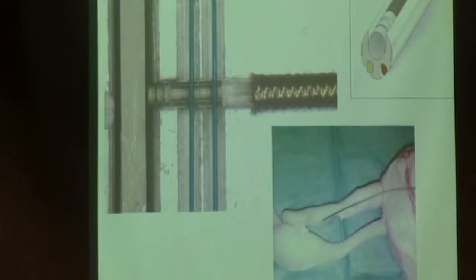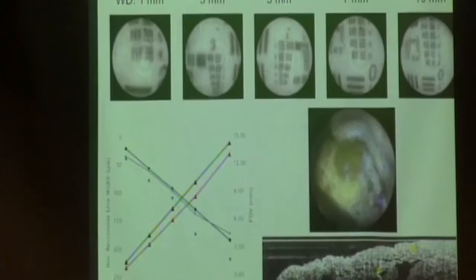It looks like, from an endoscopic view, it looks like human tissue. It kind of feels like human tissue. It's about as slippery as human tissue, and so that was really helpful for our testing. We went through and we did some performance measures of it, and it is beautiful. It really is. I'm super proud. Considering this thing is only 0.8 millimeters in diameter, you have exquisite imaging.